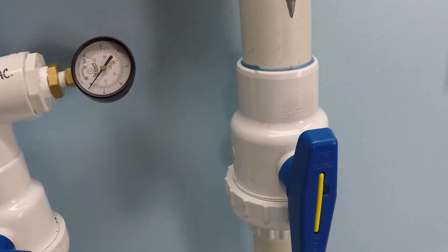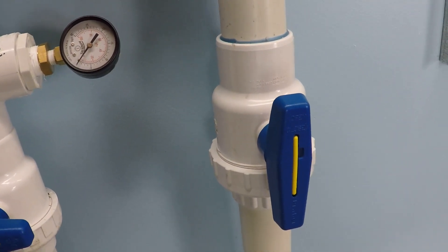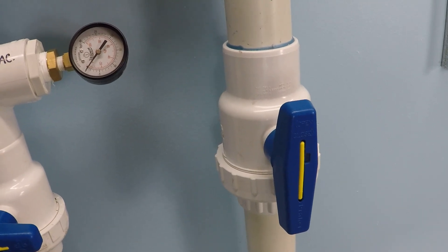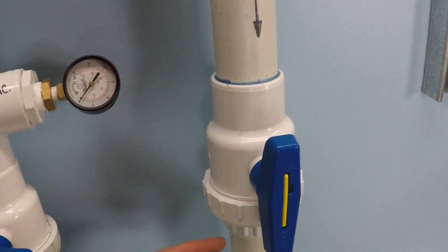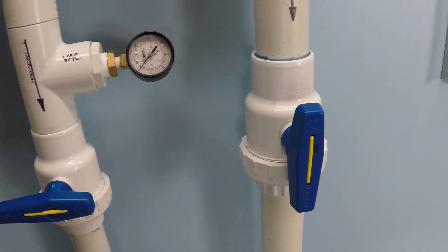So there's ones that have no union at all. So they'd look like this on both sides with no union nut in the center. I really don't like those. Anytime that somebody shows me a pool system and they're like, hey, what do you think of this swimming pool, Steve? And I see a ball valve with no union, I hate it. Forget about it. The ball valves never turn properly and they always fail early.